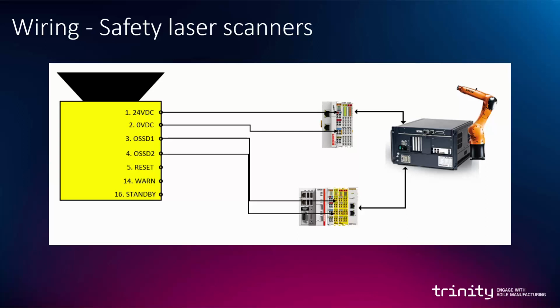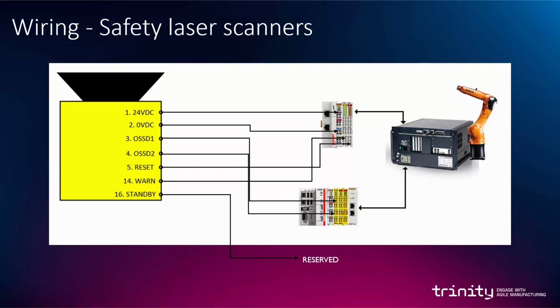The OSSD1 and OSSD2 outputs are connected to 2 different safety inputs on the safety input-output terminal. The reset input will be connected to a specified output on the basic output terminal, and the warning output will be connected to a specified input on the basic input terminal. And as for the standby input, we will leave it unconnected if we later on wish to add a standby switch into our robot system.